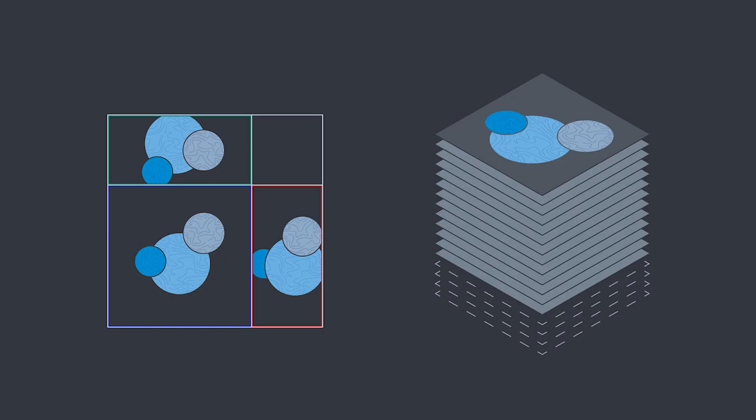So now we have these 37 images from different perspectives — but how do we get an actual dataset out of it that we can use? That's a great question. You can keep all this raw data of the 37 different images, but this really gets turned into a 3D volume by a deconvolution-based processing step that gives you a Z-Stack, just like what you're used to getting from an LSM system. So this really gives us a complete Z-Stack in a snap, in an instant — and nothing is as fast as instantaneous.